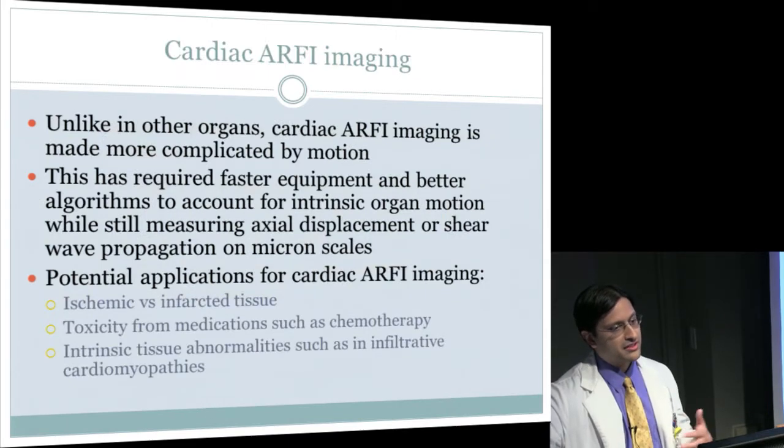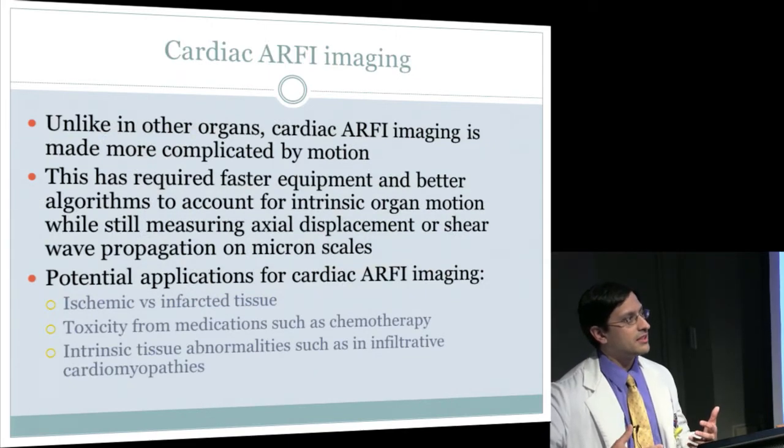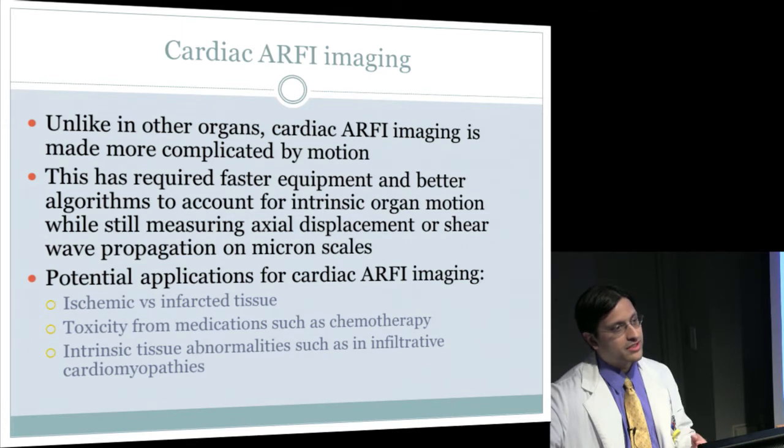Now, one of the reasons that cardiac ARFI to date has not been fully examined is that it's much more complicated than these other organs, for obvious reasons, in that it has intrinsic motion. So we're trying to measure axial displacements in the range of microns when a heart can move whole centimeters. So it's required a lot of technical advances as far as software processing and actual algorithms to be able to filter out intrinsic cardiac motion and measure true displacements.